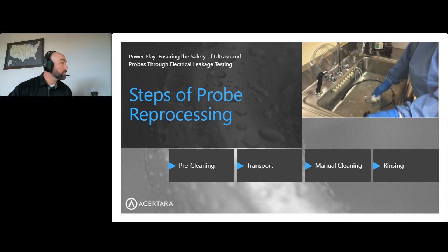So let me make sure I've covered everything that I was hoping to there. Manual cleaning and decontamination, rinse the device. Make sure that you remove any leftover debris and also all the chemistries used to clean. And just to keep saying it, in all the steps that you're going through, it's critical that you follow the probe manufacturer's instructions for use. They define the required steps for reprocessing and the compatible disinfection methods. And once we've gone through this initial cleaning, most of these probes require high-level disinfection, and so they go to that disinfection stage.